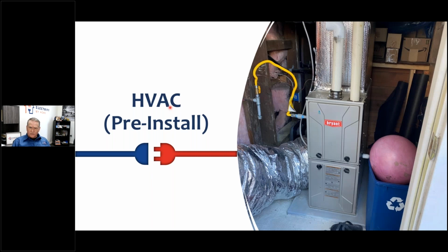This was their furnace for the downstairs system before, and you can see how lazy the duct is here. That was part of what was going on with it. It had too small of a return, and all the ductwork was not connected properly in this closet. This one presented a bit of a problem because the ductwork snuck between the floor and ceiling of the two condos, so we weren't able to actually replace that ductwork.